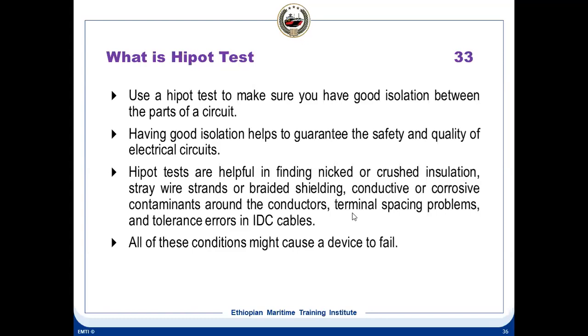Like normally a motor contactor in the starter. Sometimes the contactor does not make and break, it is not breaking. So you always check whether, when you release it, it is breaking or not. That is also a potential test. You are applying a potential and seeing that there is good isolation. So this is just the opposite of a continuity test, where you check whether continuity is there in a cable or not. So the high potential test is for checking good isolation.